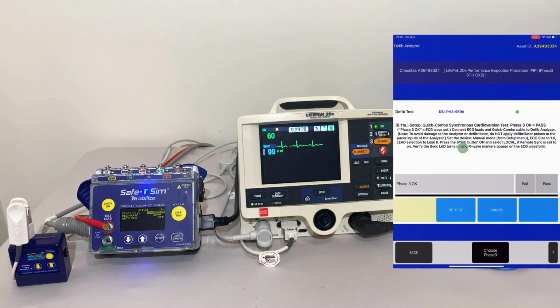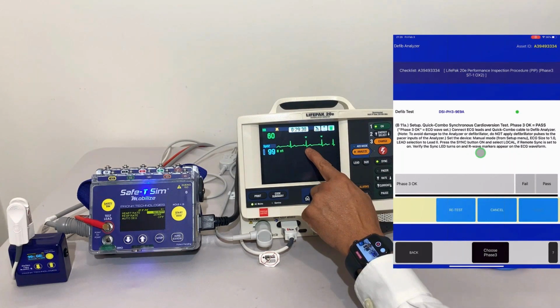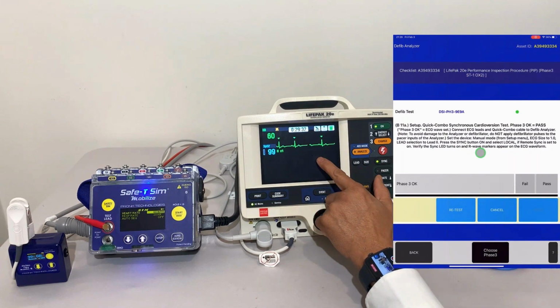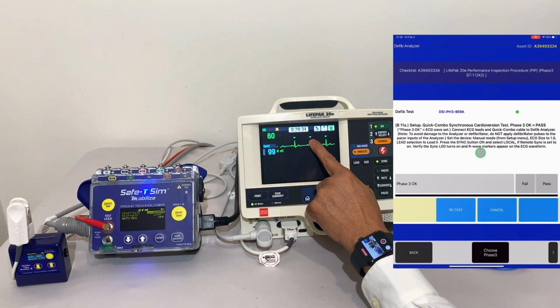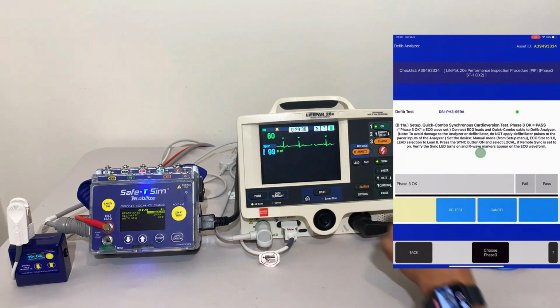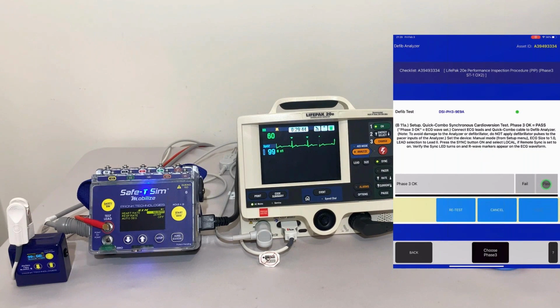Then we want to press the sync button, according to the information here on our procedure. It instructs us on what to do. We're going to press the sync button and verify that we're able to detect the R wave and display the green arrow above the R wave, to confirm that we're seeing the R wave markers appear on the ECG waveform, which we are. So we've passed this test and we go on.